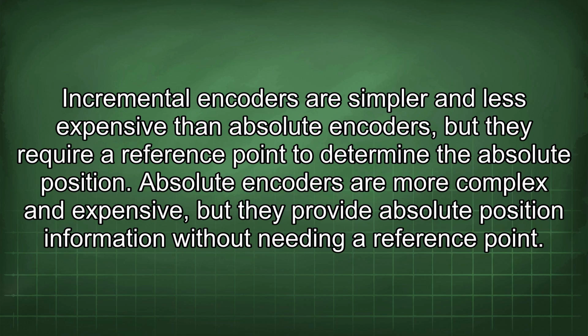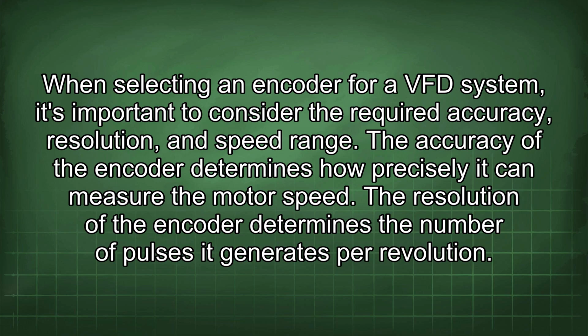reference point. When selecting an encoder for a VFD system, it's important to consider the required accuracy, resolution, and speed range. The accuracy of the encoder determines how precisely it can measure the motor speed. The resolution of the encoder determines the number of pulses it generates per revolution.